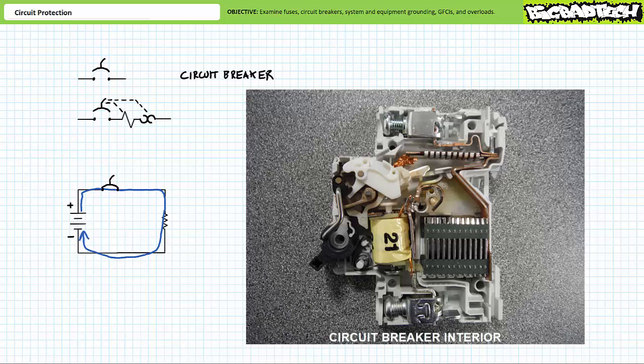Vacuum circuit breakers have nothing inside them to ionize in the first place, and the arc is extinguished upon opening. Opposite to this methodology, an air circuit breaker uses compressed air to blow out the arc like a birthday candle. All these methods share the same goal. They terminate arc current very quickly.